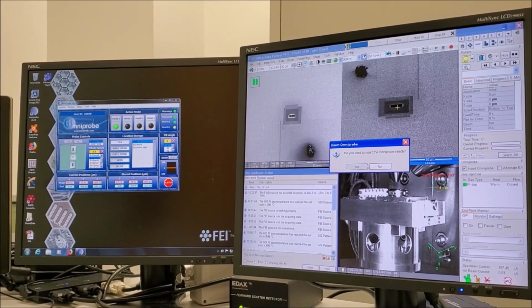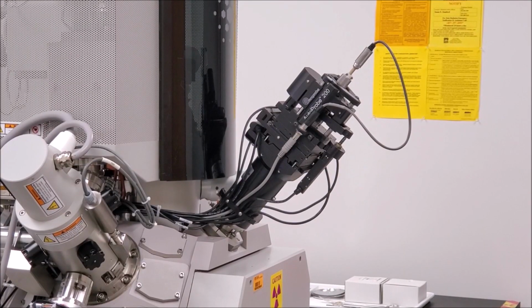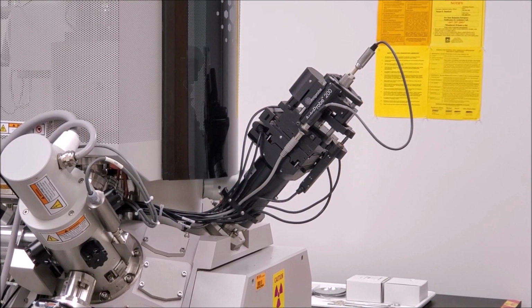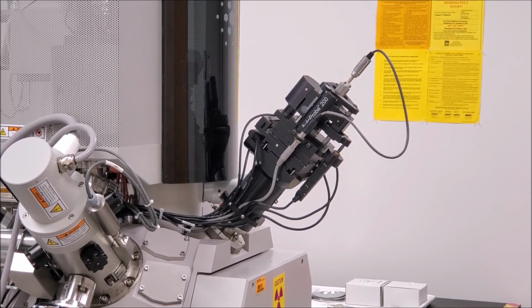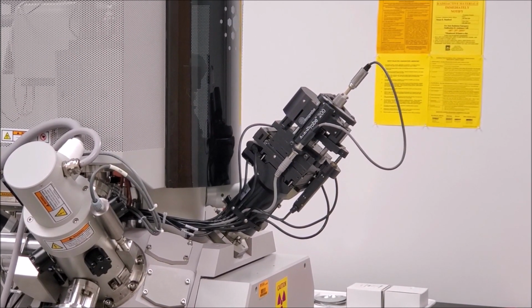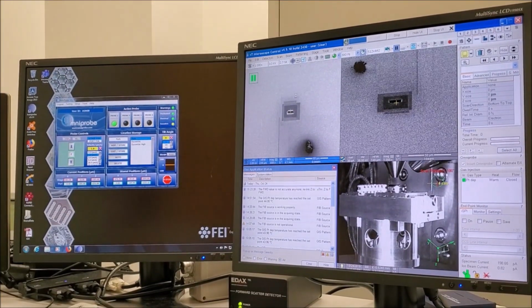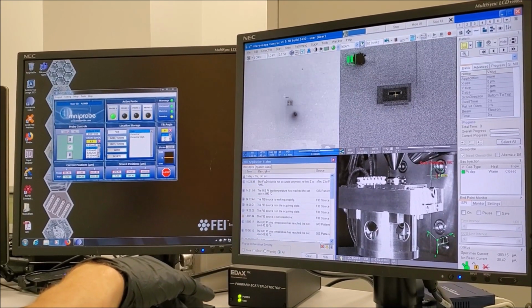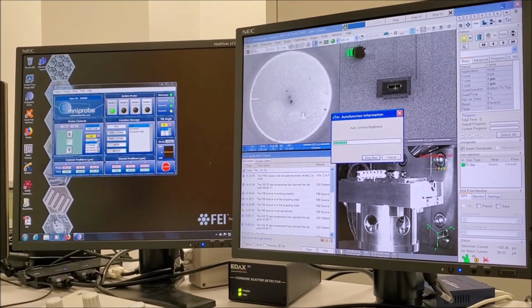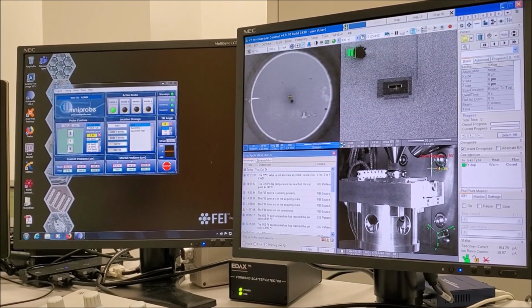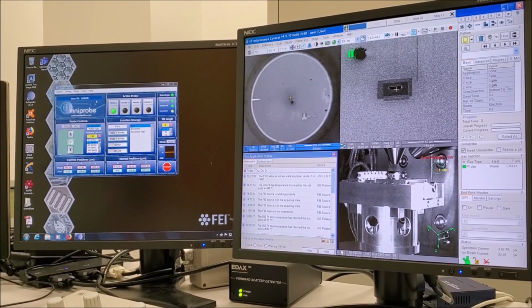In the patterning module under OmniProbe, check Insert OmniProbe to insert the OmniProbe. You can visually verify insertion of the OmniProbe on the exterior of the FIB chamber. Activate the electron beam image, unpause it, and then mag all the way out. You should see the OmniProbe on the far left side of the image.